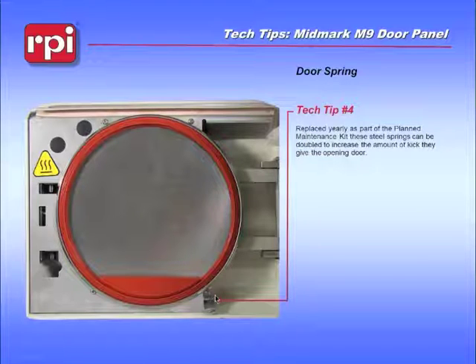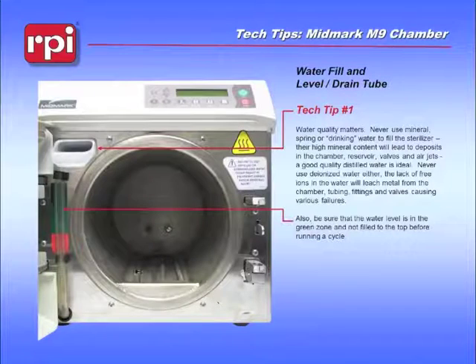Okay, now we're looking at the front of the machine. This is where the water is put into the machine. Water in sterilizers is very important. You need to be using only distilled water. You do not want to use mineral water, spring water, drinking water. All of those contain dissolved minerals that will accumulate on the chamber of the machine, on the instruments of the machines, and within the valves.